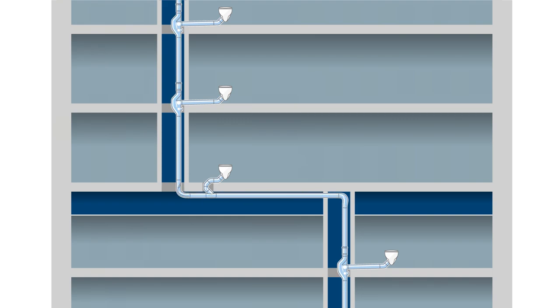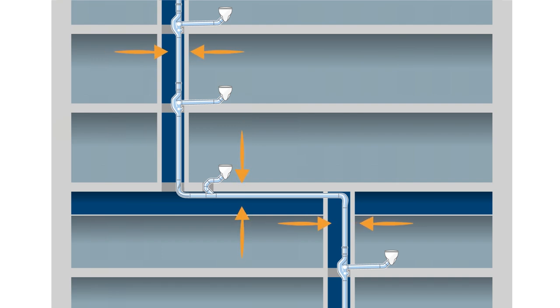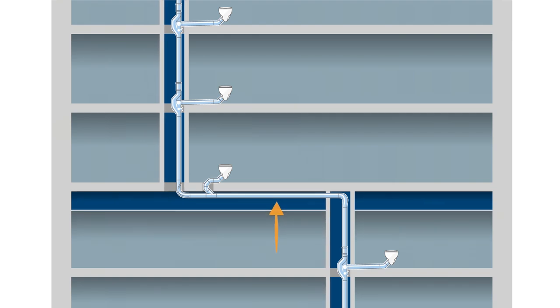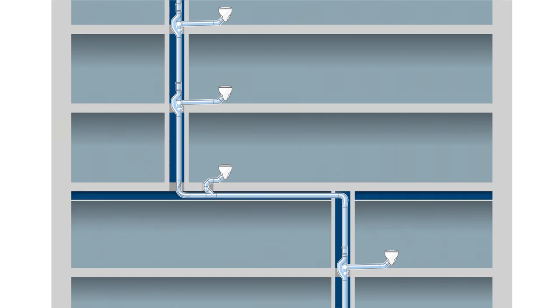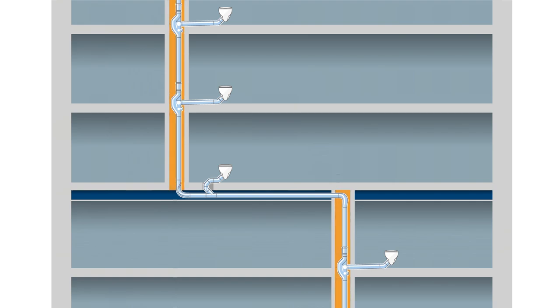The diameter of the pipelines can be reduced to D110, and horizontal pipelines up to 6 meters long do not require a slope. This equates to a space saving of up to 20 percent in the vertical duct.